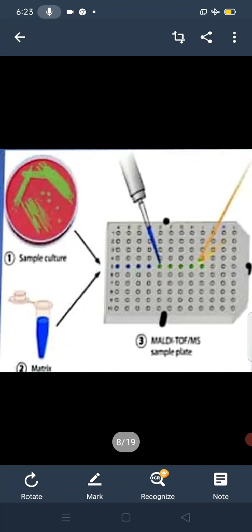Next, let us know about the laser light that is used in MALDI-TOF. Numerous gas and solid state lasers have been developed for use in MALDI. Most MALDI devices use a pulsed UV laser, that is a nitrogen laser at 337 nanometer, and neodymium, yttrium, aluminum, garnet that emits at 355 nanometer and gives a longer pulse time. IR lasers are also used in MALDI. The most common IR laser is the erbium doped yttrium aluminum garnet that emits at 2.94 micrometer. It is softer than the UV, which is useful for certain biomolecules.